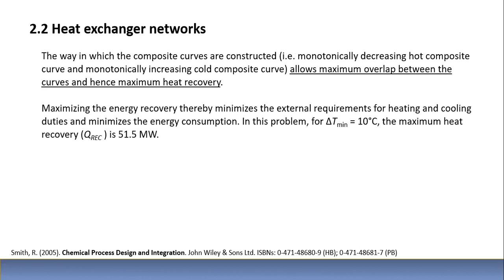Yes, we will need less capital investment in heat exchangers and less capital investment in heat exchanger area, but there will be a price to pay in the amount of minimum energy required as input into the process, and there will be a price to pay in the amount of energy that will need to be absorbed from the waste heat coming from the process. Just like you see here, the QH minimum is bigger than the QH minimum that the process required with delta T minimum of 10. And also the waste energy, instead of being 10, now is 14. So there is a price to pay when we do this.